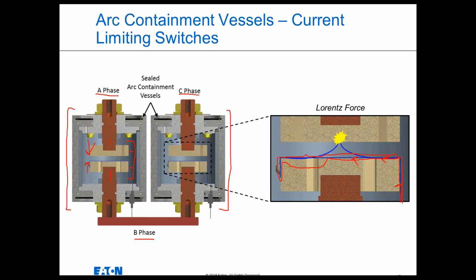And what happens when current flows through a wire? It generates a B field, right? A magnetic field. Good old right-hand rule. Let's say current is flowing from right to left across the contact. Using the right-hand rule, that's a counterclockwise magnetic force. Then that current flows back around and returns to the trigger board. Current flows in the opposite direction and generates a clockwise magnetic force. So in about 200 microseconds, the arc quenching device has created two opposing electromagnets in this little wire.